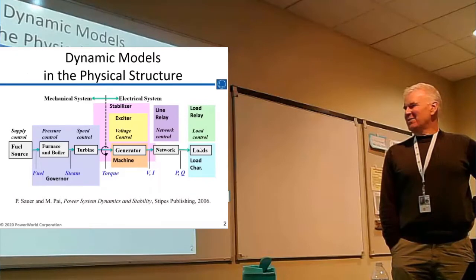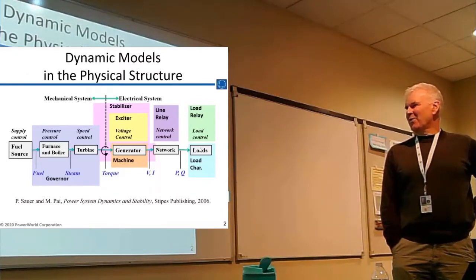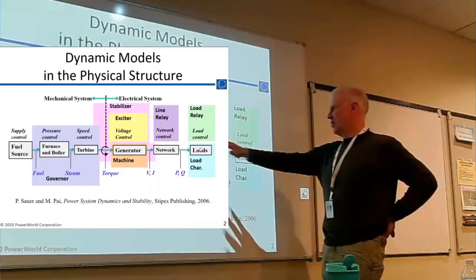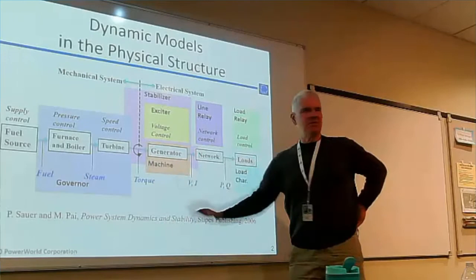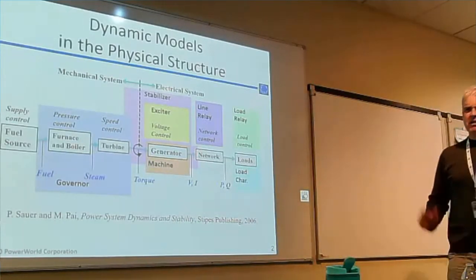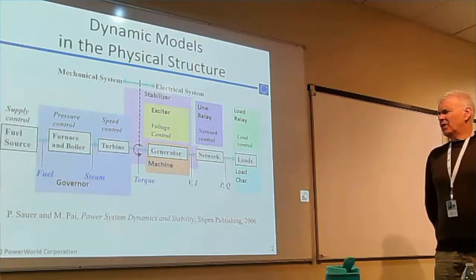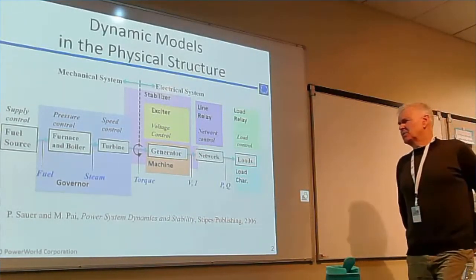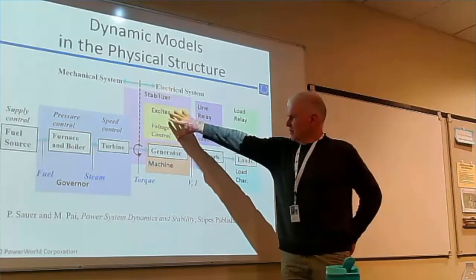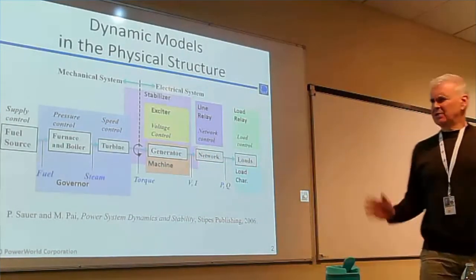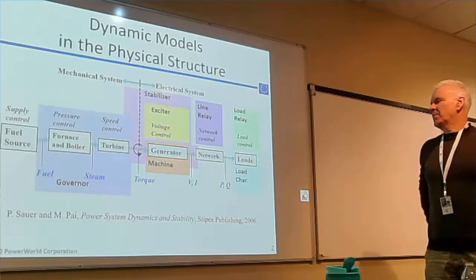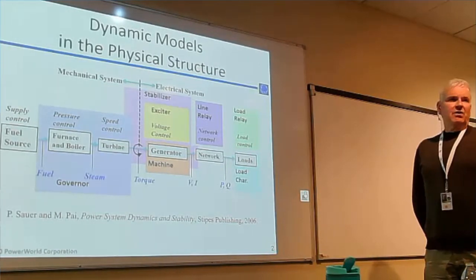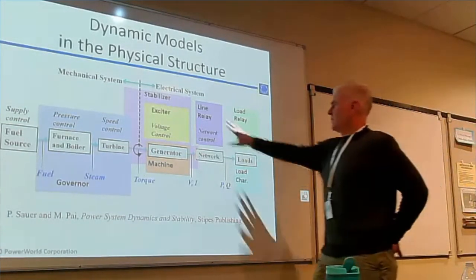We're talking about the modeling of the power grid, and if you look at how it can be broken down, on the generator side, there's a machine model, and that's what Jamie talked about, and he left us with a field voltage. The field voltage is what drives the machine, and the exciter is what controls that field voltage, taking sensing coming in from the grid and a set point, and it's controlling the field voltage ultimately. So we're going to talk about the exciters.